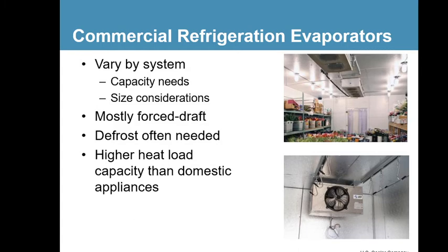Commercial refrigeration evaporators vary by system, capacity needs, and size consideration. They're usually very small and thin, so they can be in the middle of the room where you have to walk underneath them. Mostly forced draft, which means they have fans built into the bottom of them. Defrost is often needed, so it gets defrosted, I would say, probably every 20 minutes to every 45 minutes. Higher heat load capacity than other domestic appliances.